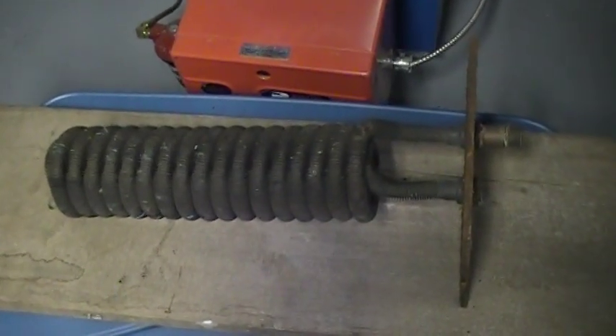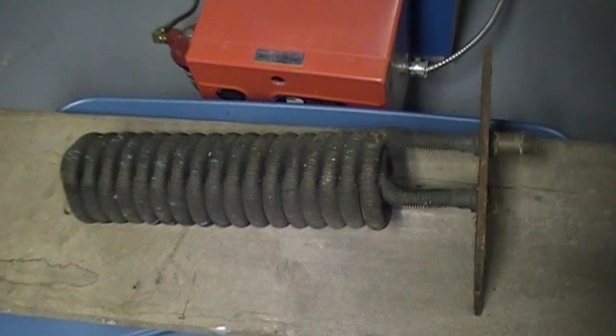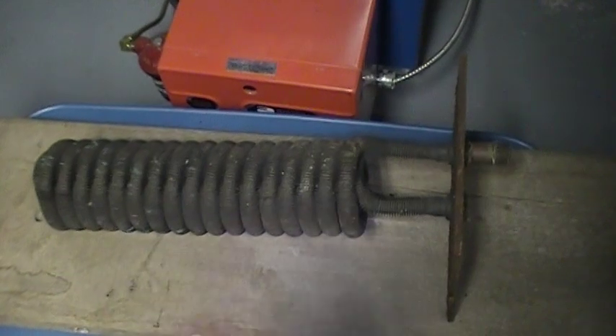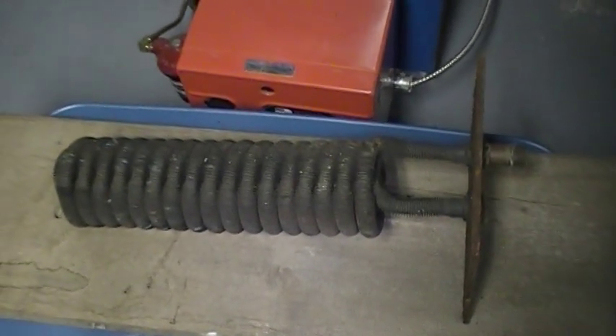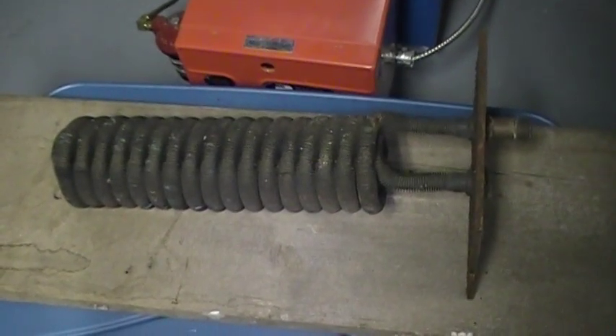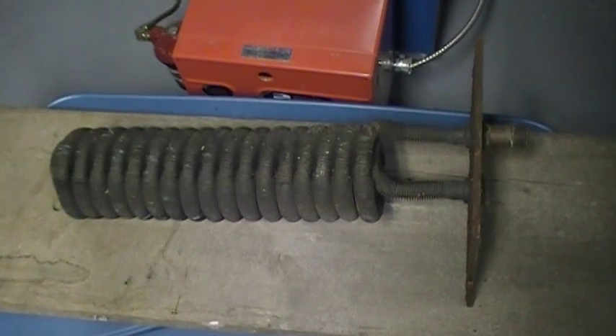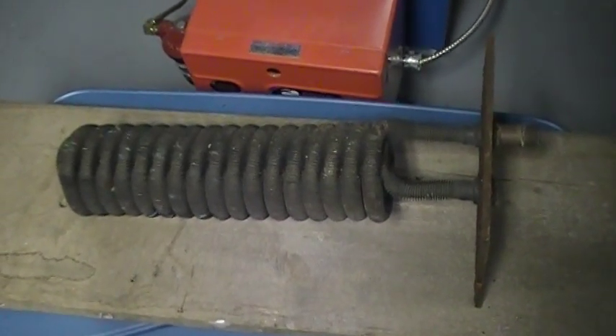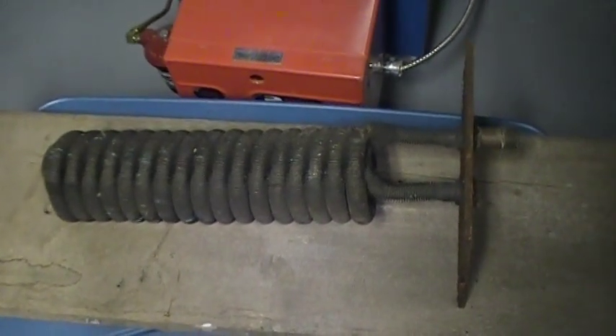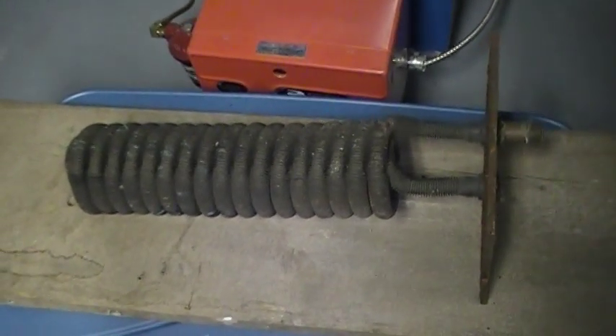An indirect hot water heater requires another zone off of your furnace, and they're becoming quite popular now. The problem with the pinhole in the coil is that it'll put your house pressure — which is considerably higher than the furnace pressure — into the system. Your furnace requires 14 to 15 pounds to operate, and your house pressure is quite a bit higher than that. Anything above 30 pounds will cause your relief valve to blow off.